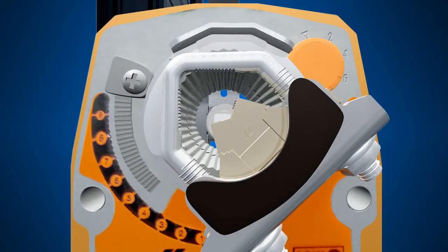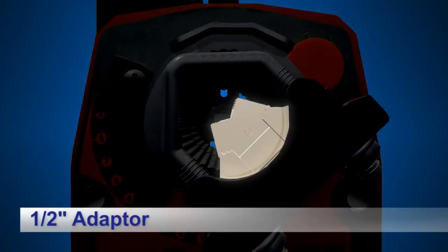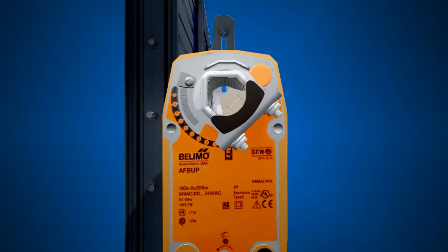A new Belimo actuator ships from the manufacturer with the 1/2 inch adapter inserted in the toothed block of the universal clamp. This adapter must be removed in order to allow the actuator to fit over the jackshaft.